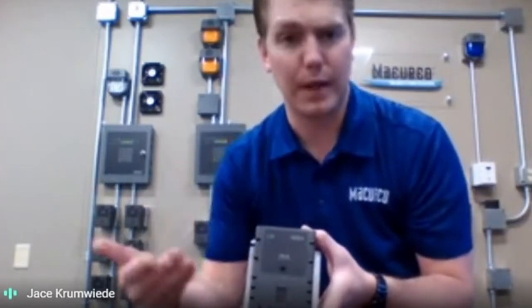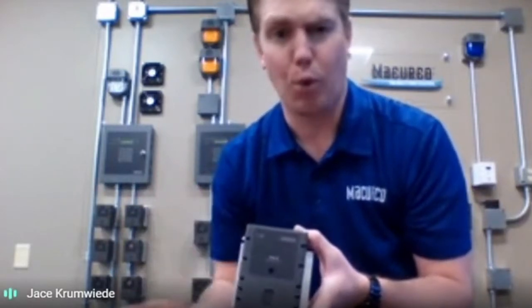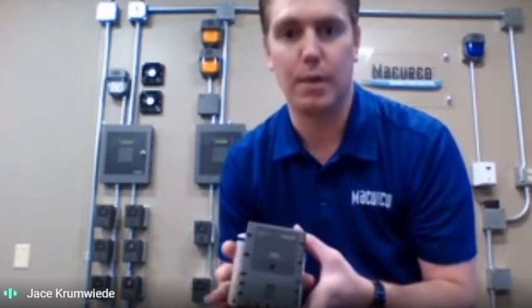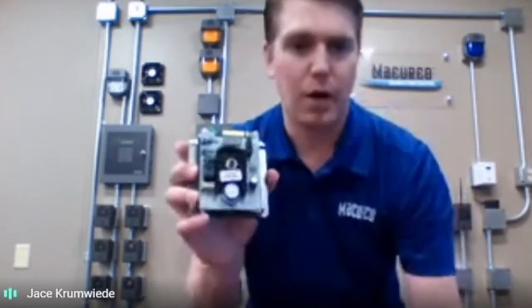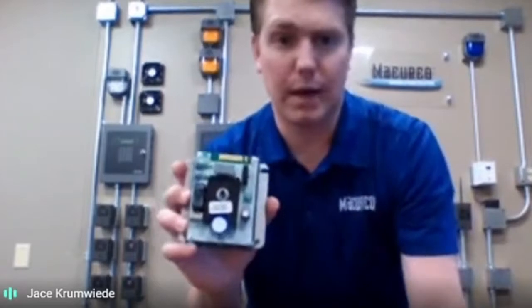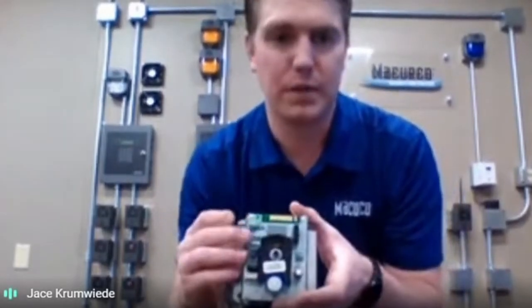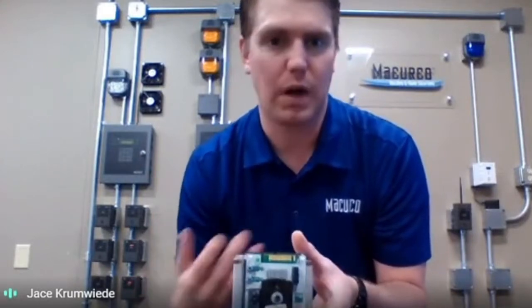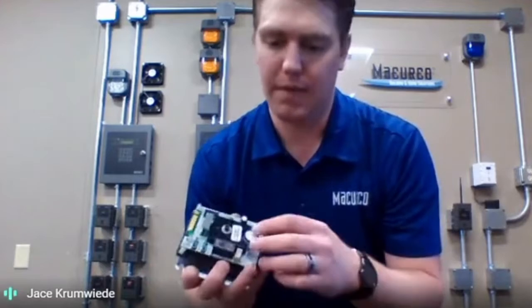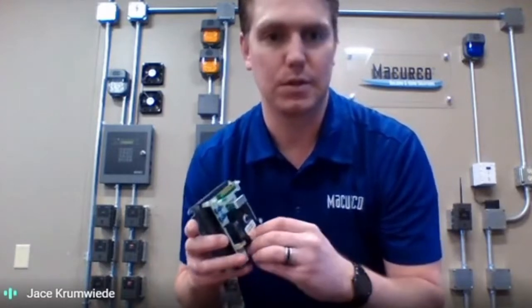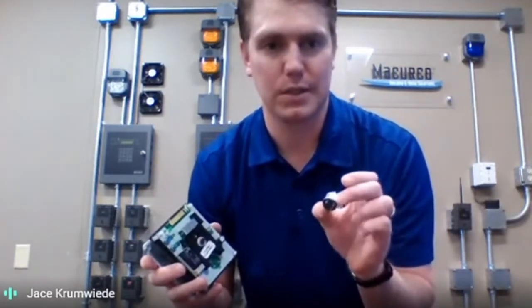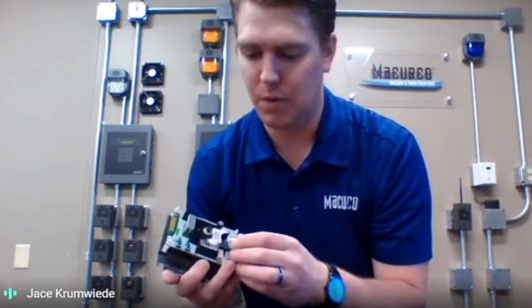They do also have a digital display, so you can see the readings in real time. Onboard buzzer as well, so you'll have that local audible alert. Slide the cover off. We'll take out a screw and slide that cover off, and then you'll have a 2-button interface to change various settings, add delays to your relays for not engaging fans right away, maybe waiting a minute or two. And then some units will have replaceable sensors, so after the life of that sensor is expired, you can go ahead, pop in a new unit, get that calibrated, and get it back on the wall.